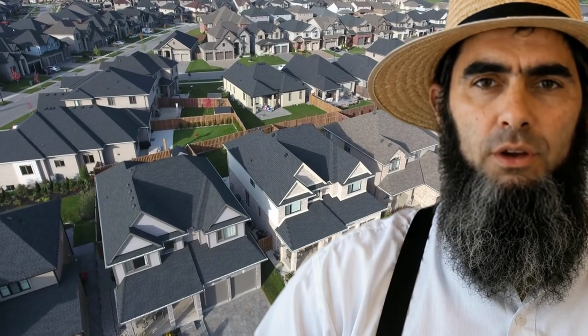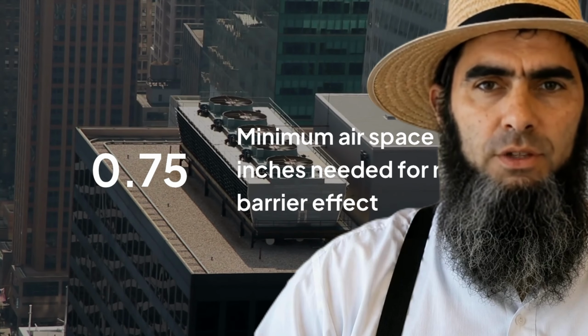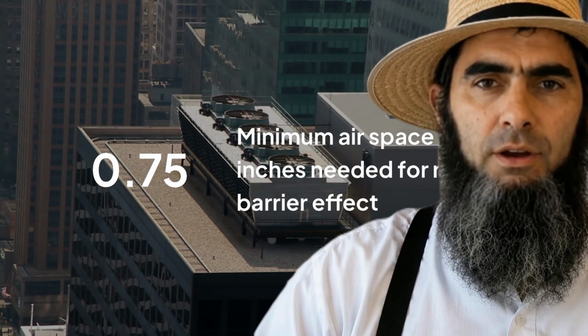You staple the foil across the bottom face of the rafters, not tight against the roof deck. That air gap is the whole game. Penn State says you need at least a 3/4-inch airspace for the surface to act as a radiant barrier. I like a 1.5-inch to 3.5-inch rafter cavity because it is common and forgiving. Leave a 2-inch opening at the soffit for intake air. Leave about a 1-inch space below the ridge so hot air can keep moving out. Overlap seams by 2 inches. Tape tears. Staple every 8 to 10 inches.